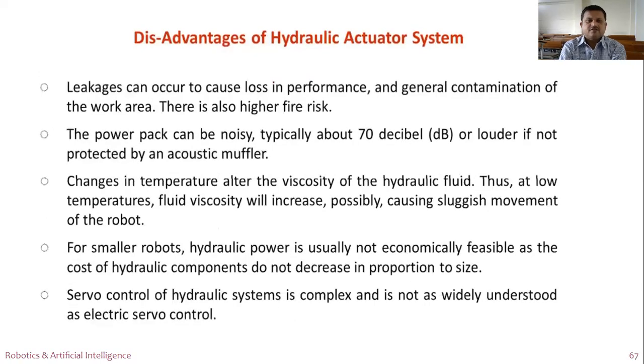Disadvantages of hydraulic actuator system. First, leakages can occur to cause loss in performance or in general contamination of the work area. There is also higher risk. The power pack can be noisy, typically 70 decibels or louder, if not protected by an acoustic muffler.